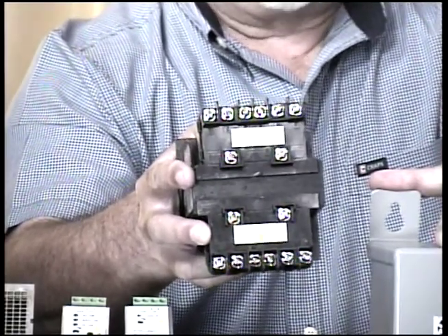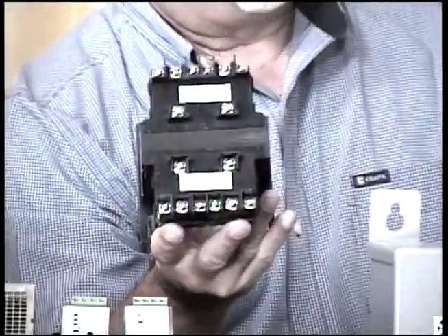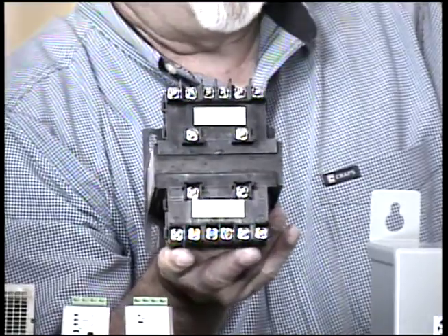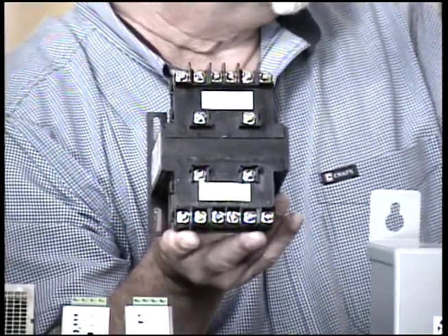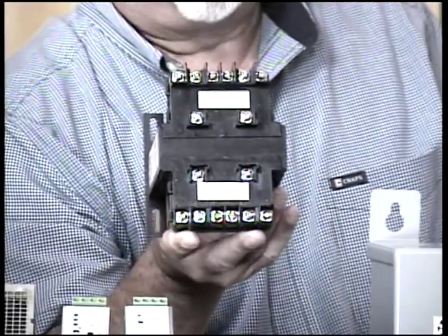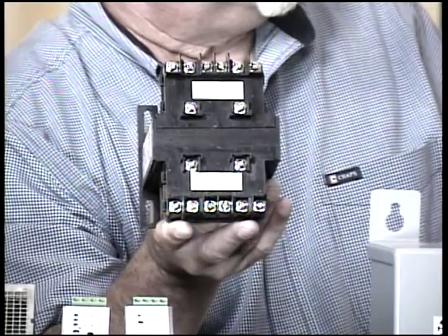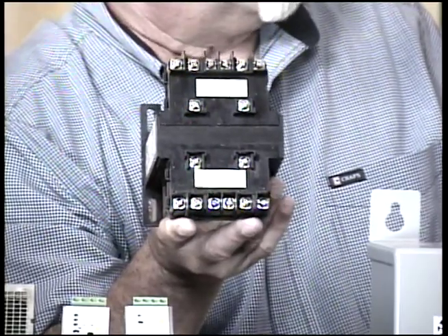These are control transformers. Typically, if you go to the next slide, I think we show these are broken down into 4 different voltage combinations, where you can do 240, 480 by a series of jumpers to bring in your incoming voltage, and on the output we can do 24, 120, 240 with a series of jumpers. I should also mention real quick, these also come with a fuse kit option.